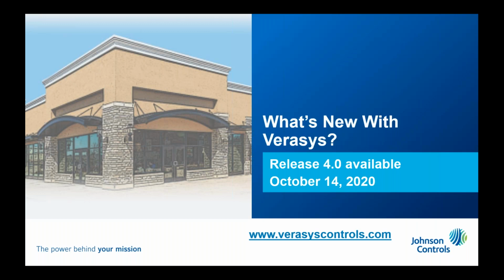Okay, great, thank you. And with the new updated NS8000s, are they able to control reheat in the VAV boxes for dehumidification? There is no sequence within the ZECs to support any kind of dehumidification at this point, so I guess the answer would be no to that.